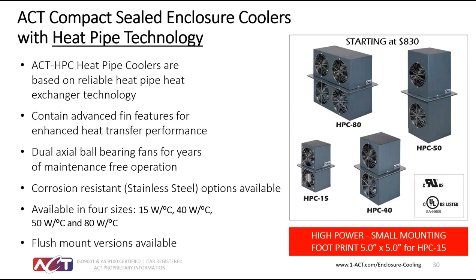Again, there are multiple sizes of these devices, ranging from about 300 watts to about 1600 watts of cooling. And again, you have all the different NEMA values and different voltage values to apply this product. The difference between the heat sink cooler and the heat pipe cooler is that it's a bit more dense package. It does react faster to a variable heat change. So if you have a high power drive system and you need to address that drive firing up very quickly, and you want to make sure there's no false trip, the heat pipe cooler may be a better choice.